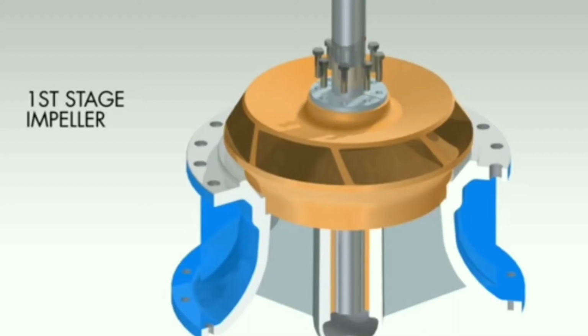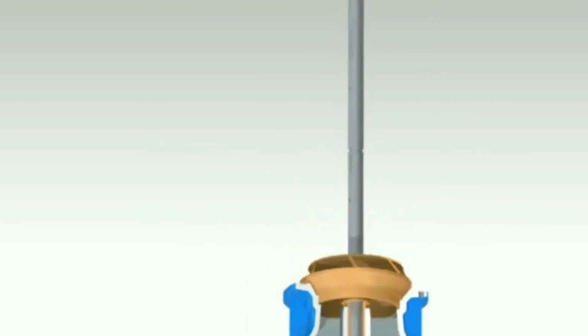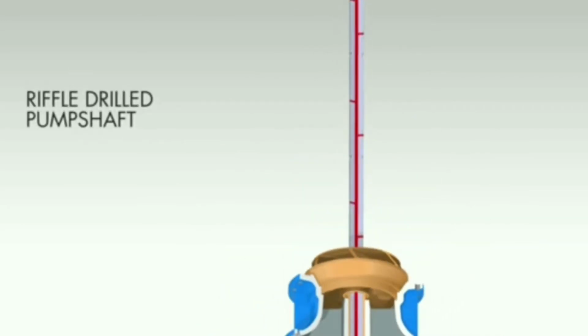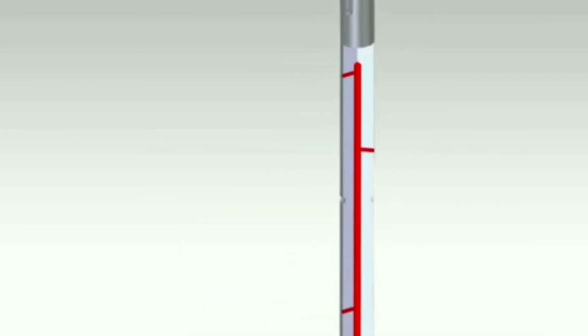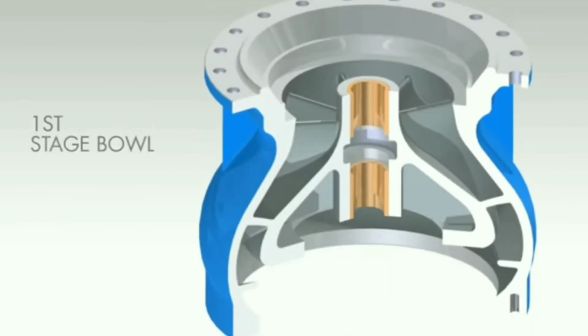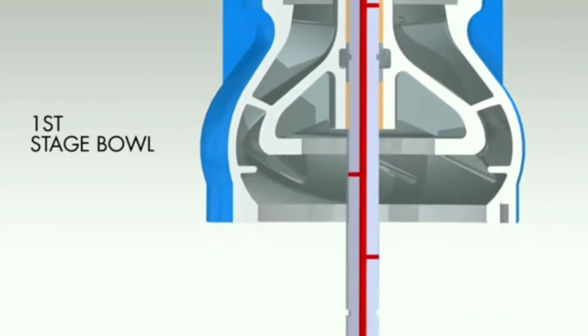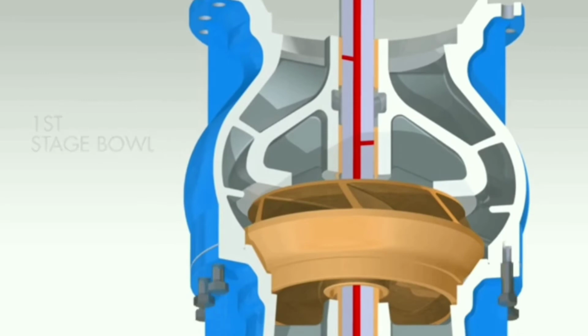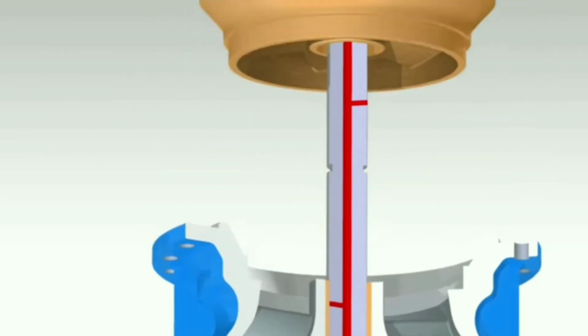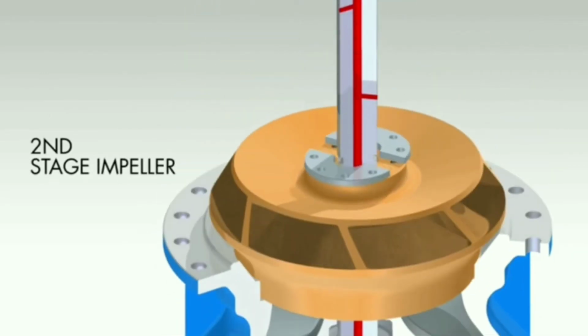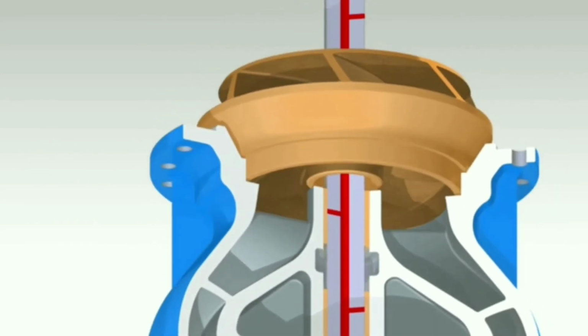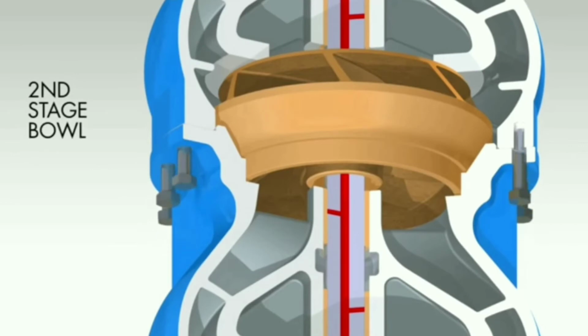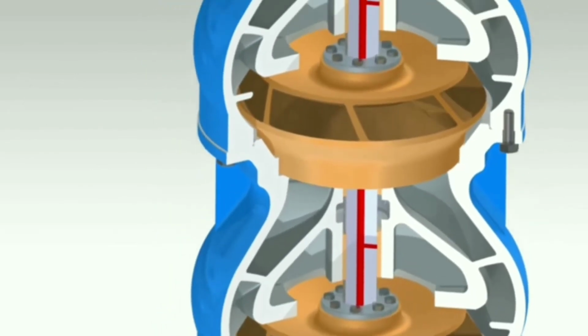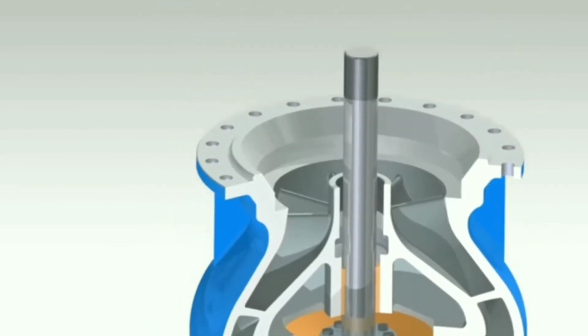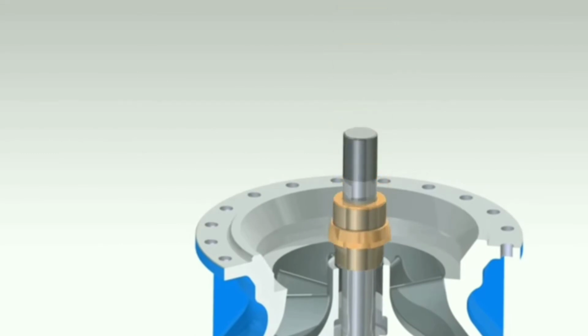The pump is usually driven by an induction motor or by a diesel engine through a right angle drive. The pump end consists of a rotating impeller attached to a shaft that directs the well water into a diffuser casing called a bowl. A multi-stage configuration uses multiple impellers on the same shaft to create the higher pressure needed for deeper wells or higher pressure requirements at ground level.